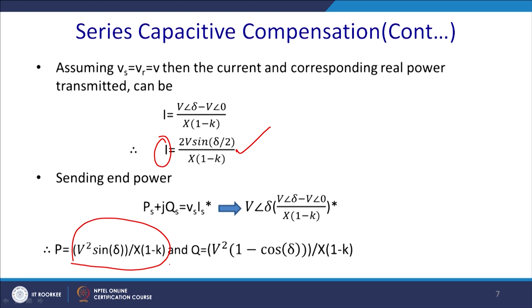So, if k is 0.5, straight away you have a twofold increase of your real and reactive power. In the same way, whatever power has been sent will be received. So, we can write the receiving end power Pr and Qr, given by Vr into Is, because Is will be the same. There is no shunt compensation, so the current through all the elements would be equal. So, the same value you get, ultimately V square sin delta by X (1 minus k), and similarly for the reactive power.